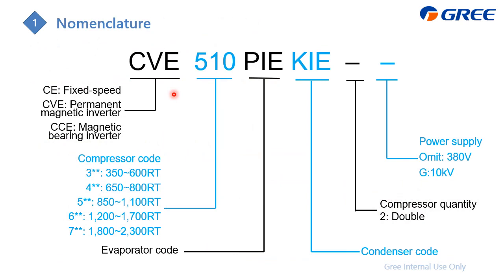And this is how we name the centrifugal chiller. This part is the series name, either CE, CVE, or CCE. This number is the compressor code. According to different capacity, the code is also different. And this is the evaporator code. And this one is the condenser code, and with different combinations, the code is also different. And this one is the compressor quantity. Two means there are two compressors. And the last one is the power supply.